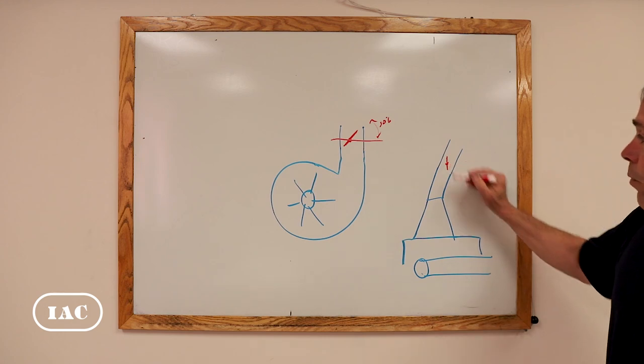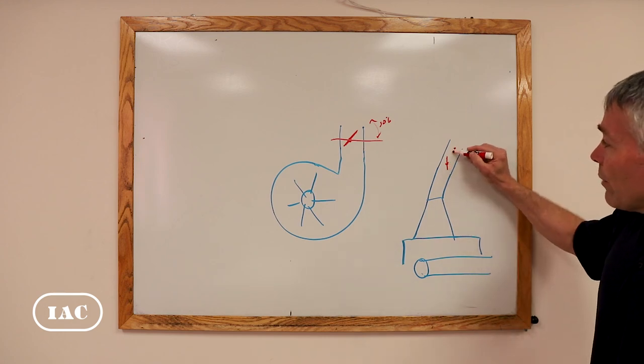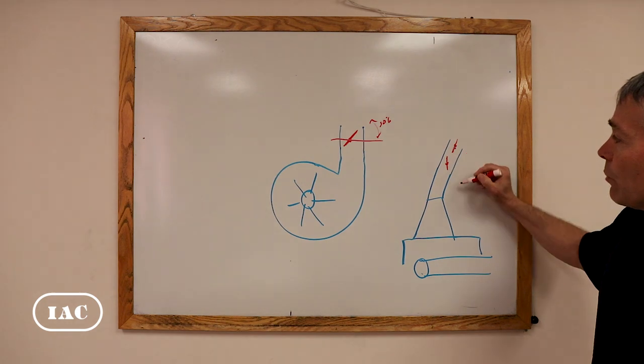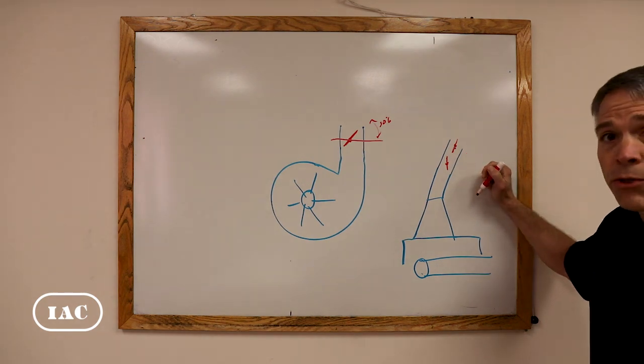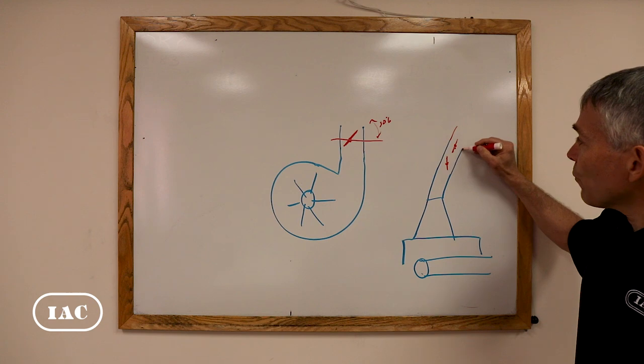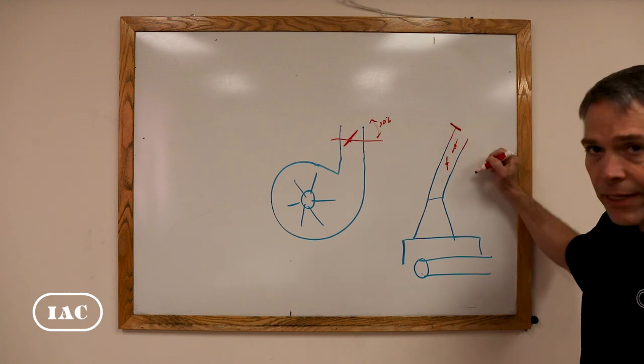In here, one of the disadvantages about butterfly dampers is that when it's completely open in this position, you think that there's no restriction to flow when in fact there is. So, a lot of times for ductwork, we recommend guillotine dampers.